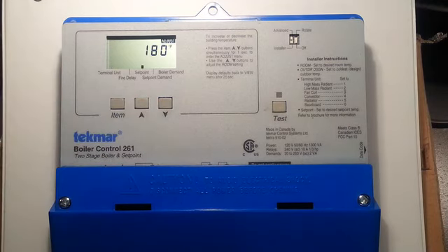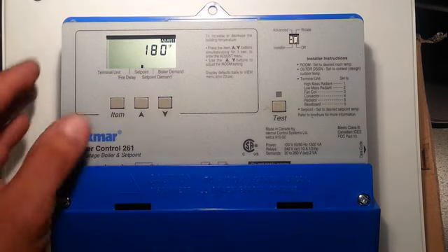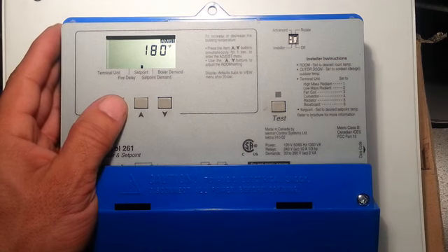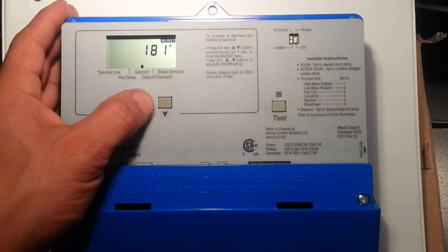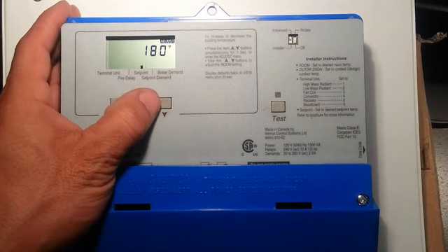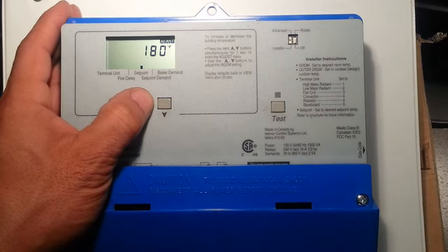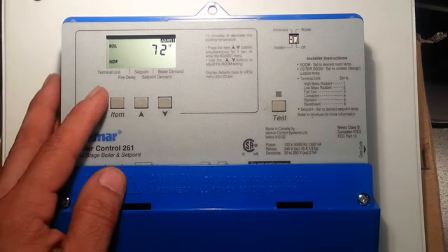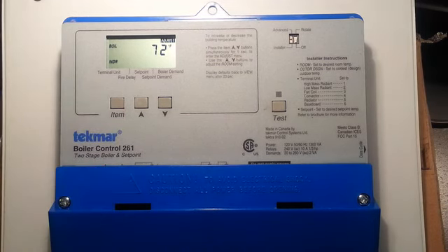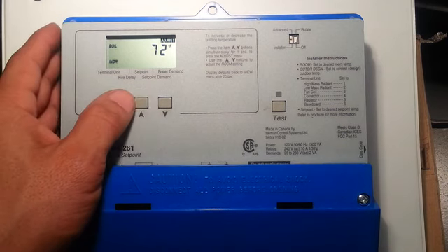The next setting is the set point setting. This one is set at 180 degrees. This is only used if you're running a domestic hot water system off the boiler heating system. So typically not used, but if you were, you would need to have an individual set point demand, and then you would set this at roughly 180 or whatever the inlet heat exchanger water temperature was set at. Like I said before, the next setting is boiler indoor temperature, which is set the same as the room occupied temperature. The starting set point is usually 72 degrees.